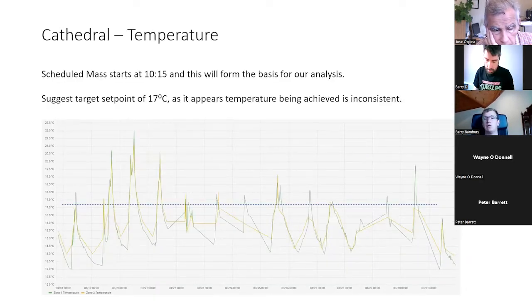One of the other big things we noticed, we really weren't expecting this, was when we looked at the temperature over time. We were saying 17 degrees would be a good goal for the church, what we should be aiming for inside there. Not only was it reaching it on most days, it was actually exceeding it. And some days you can see it here getting up to 20 degrees Celsius and 22 degrees Celsius. The only time this was possible was when the gas heater was left on for maybe 10 or 15 minutes or maybe 30 minutes too long. Just bear in mind the vast volume of air inside this space, the amount of energy it takes to raise it by a couple of degrees is very substantial. So with our operational recommendations, we'll be putting in safeguards so that hopefully this won't happen again in the future, because it's very expensive to heat that volume of air up to 22 degrees Celsius.